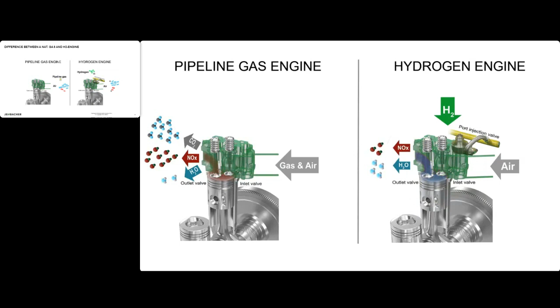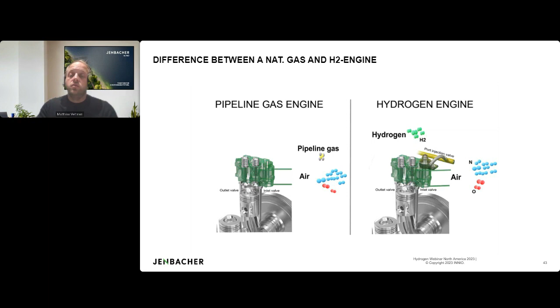Another advantage is that we can correct the amount of fuel per cylinder individually on a cylinder-selective basis, also leveraging the pressure-based control we have on our hydrogen engines. We have very good transient performance because we can quickly adjust the fuel ratio if we need to pick up or shed power in an island mode application.